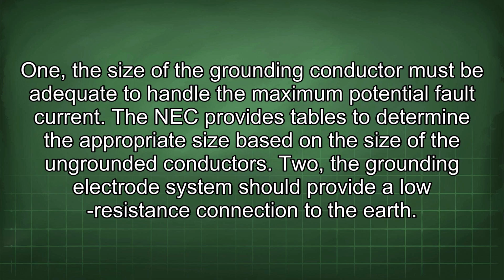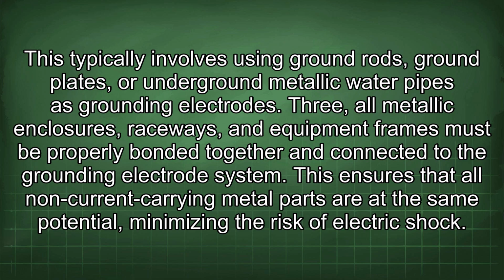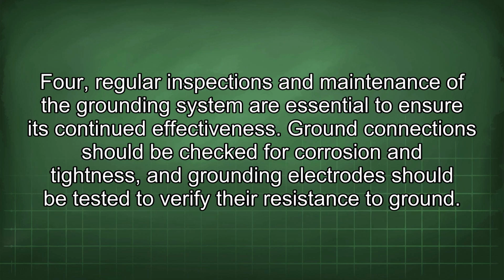2. The grounding electrode system should provide a low resistance connection to the earth. This typically involves using ground rods, ground plates, or underground metallic water pipes as grounding electrodes. 3. All metallic enclosures, raceways, and equipment frames must be properly bonded together and connected to the grounding electrode system. This ensures that all non-current carrying metal parts are at the same potential, minimizing the risk of electric shock. 4. Regular inspections and maintenance of the grounding system are essential to ensure its continued effectiveness. Ground connections should be checked for corrosion and tightness, and grounding electrodes should be tested to verify their resistance to ground.